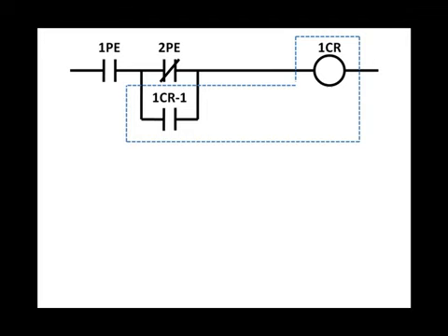But once the relay is energized, the circuit can complete through normally open contact 1CR-1 from the relay itself. Therefore, 2PE normally closed contact could go false and the relay will remain energized, because the relay's normally open contact 1CR-1 has sealed in the temporary condition of normally closed 2PE.